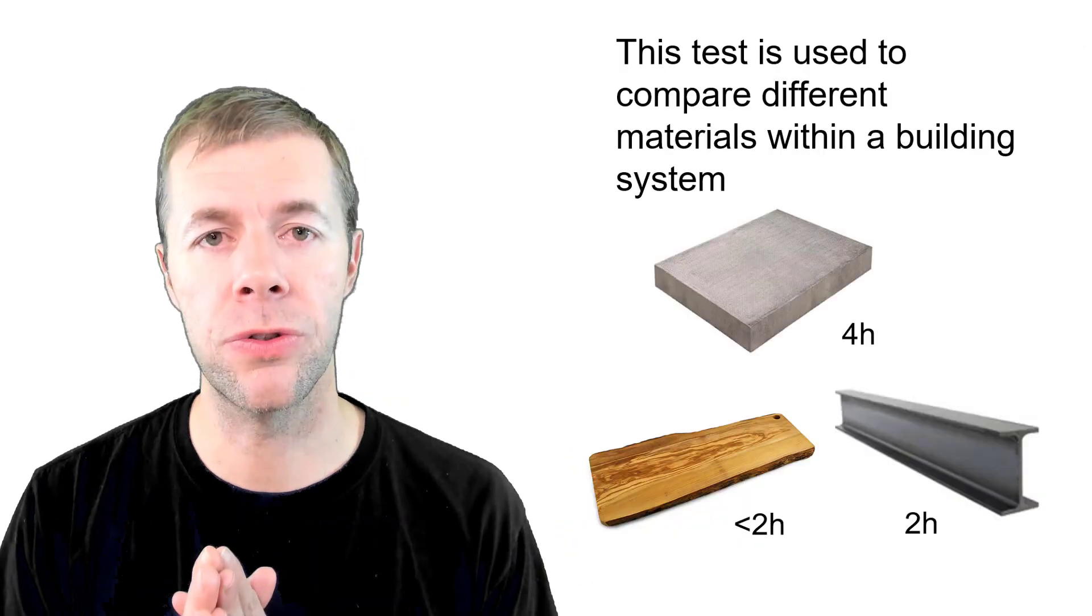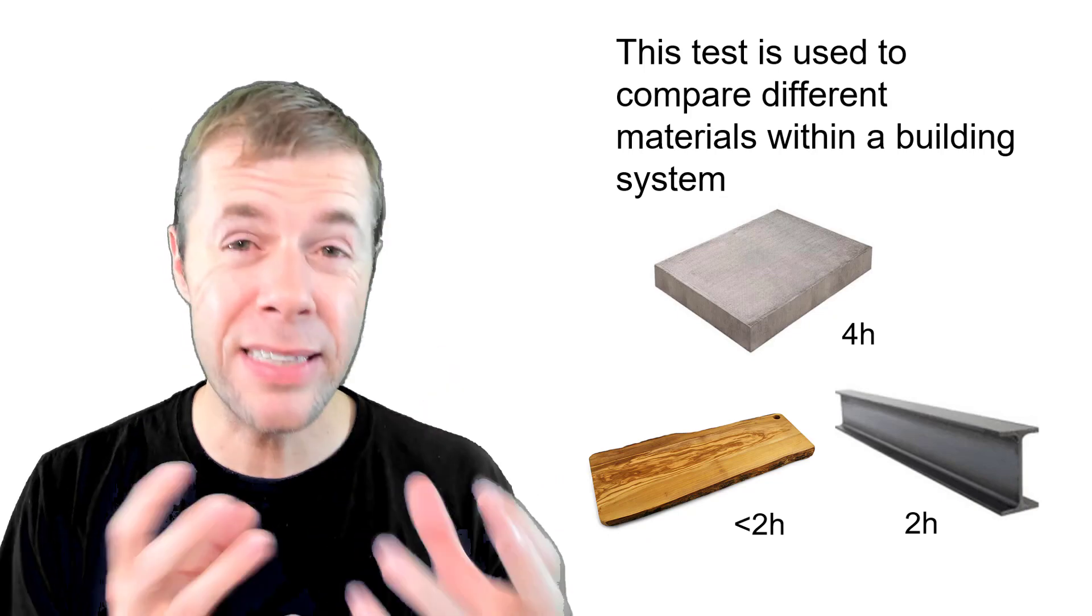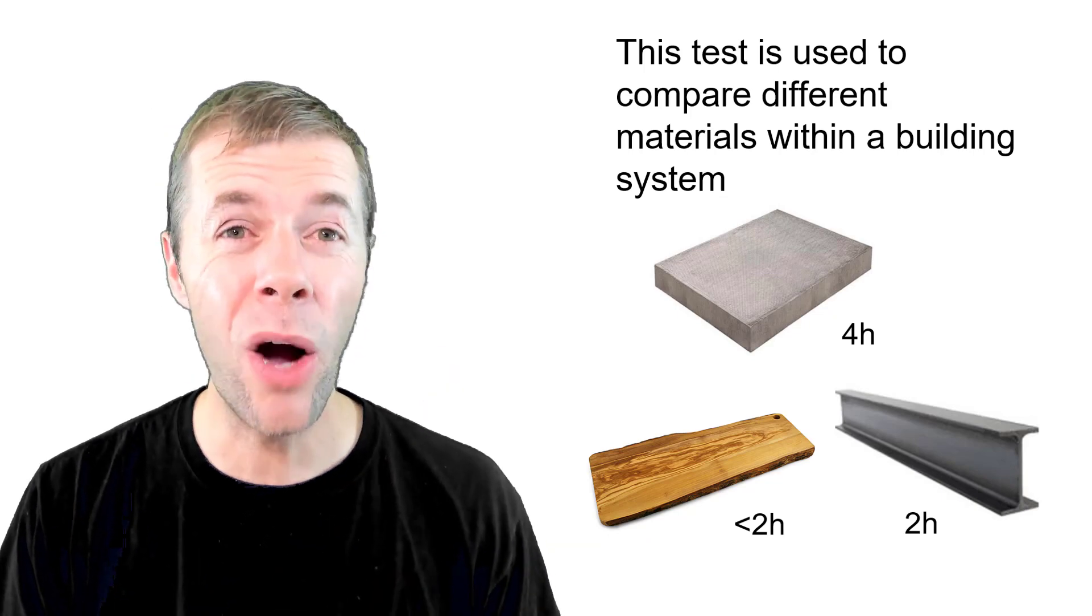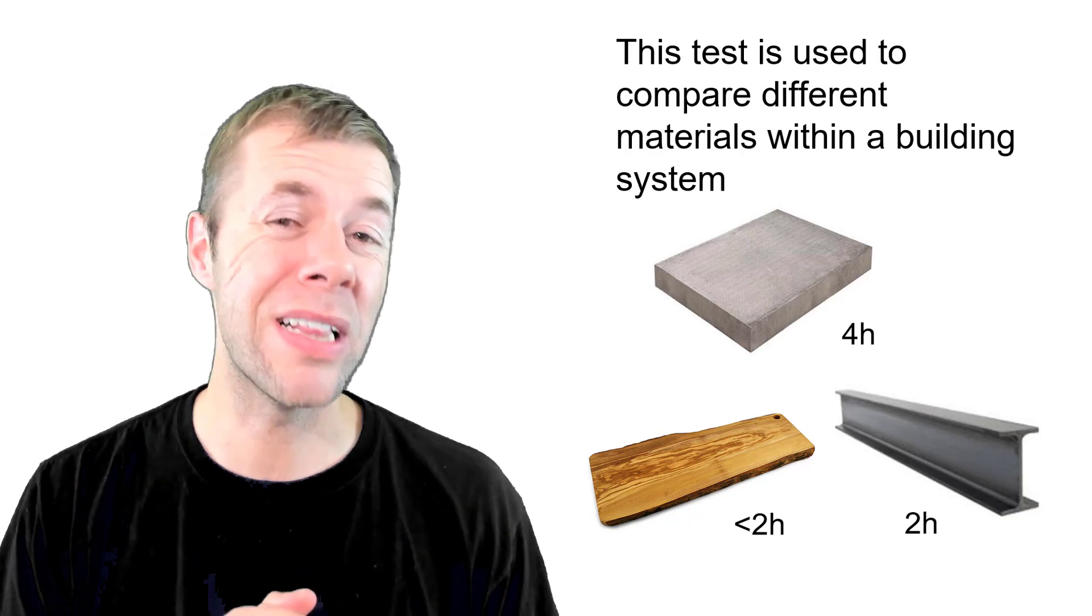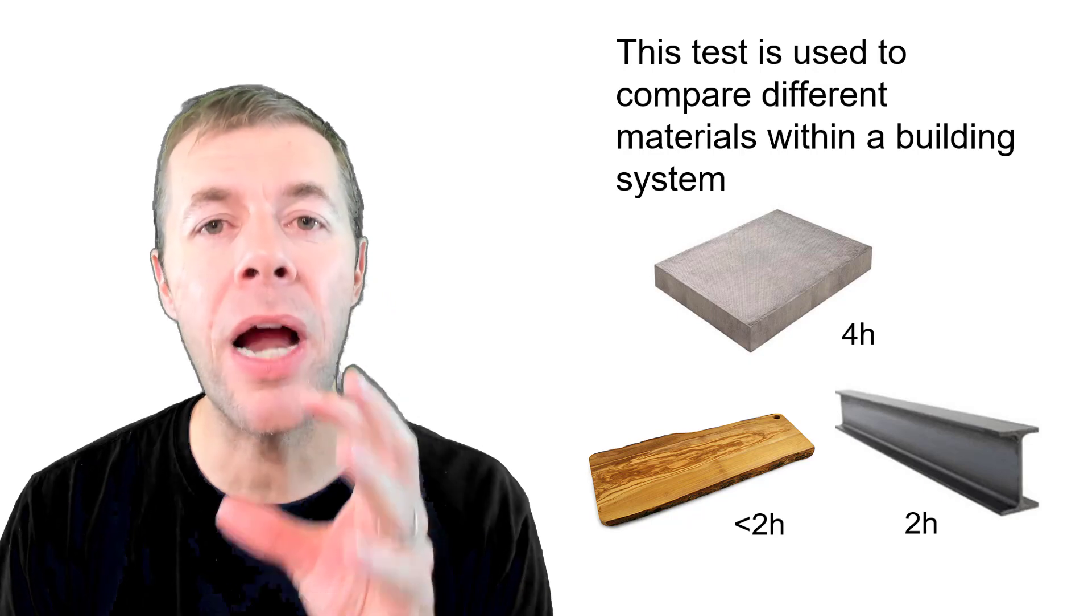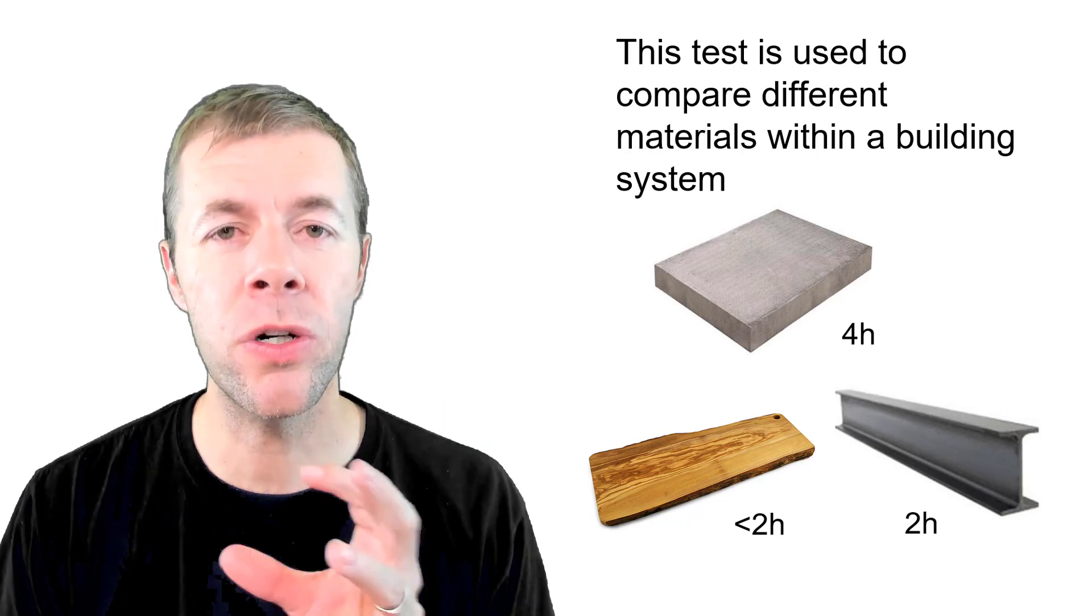So we can compare different materials. We can compare like concrete's typically about a four hour fire rating, steel is usually around two hours, and wood is usually less than two hours, sometimes as low as one. Again, it's comparative so we can compare these different materials to one another.